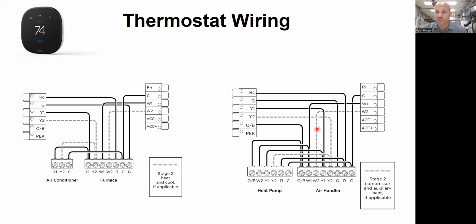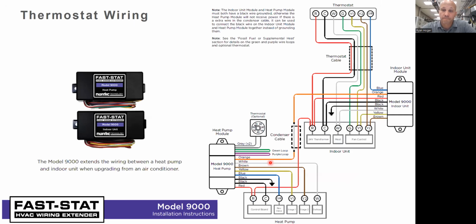So on a heat pump upgrade from a straight AC, I will need at least 1 extra wire for the reversing valve from the thermostat to the indoor unit. And then from the indoor unit to the outdoor unit, I will need 5 wires instead of 2. So I'm going to need to pull additional wire. If you don't want to pull additional wire, that is okay. There's options around that. Specifically, you can get one of these kits.